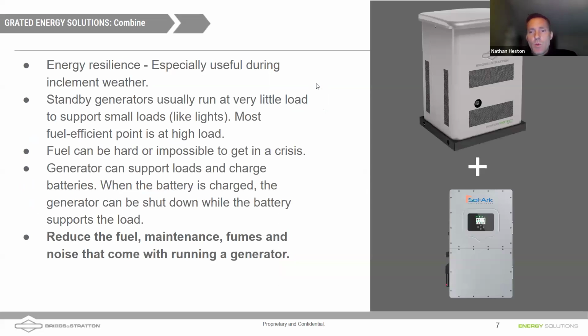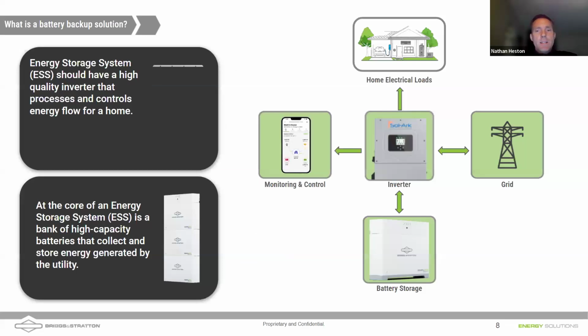We are seeing more and more systems when you combine it with a Sol-Ark, where you're having both generators and potentially solar, but both generators and batteries working together for hybrid systems. And this does a number of things. It reduces runtime on the generator. It burns a lot less fuel because you can run that generator at more optimal, higher loads, which are more efficient at producing kilowatt hours. And so you're saving fuel, you're saving runtime, you're saving maintenance on that generator, and you're generating electricity at more efficient and cost-effective prices. So understanding where we're coming from with that background, backup systems have traditionally, for the past 40 years or so, been generator-based systems.